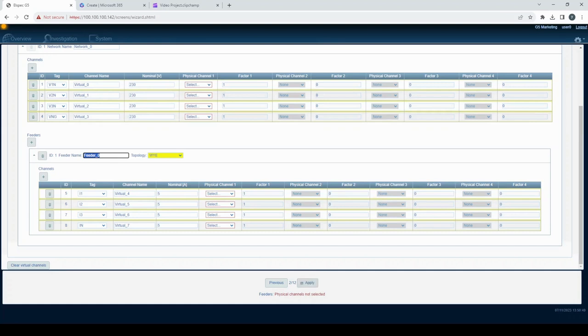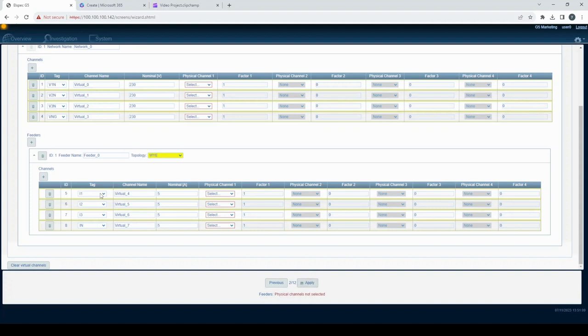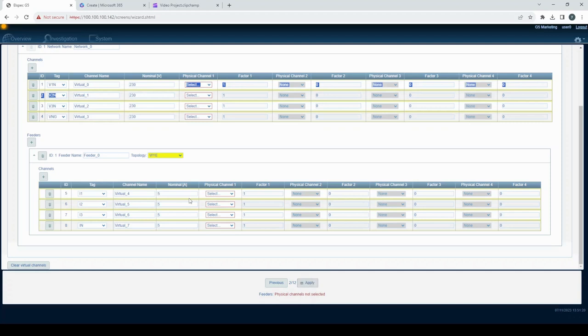Pressing on the add virtual channel button allows you to add virtual channels. To remove a virtual channel, press the remove channel button. You can customize the channel name to make it easy to identify. The channel tag is essential as it defines the electricity meaning of a virtual channel. The nominal value of a channel is used to select the network voltage or current level for a PQ event reference.